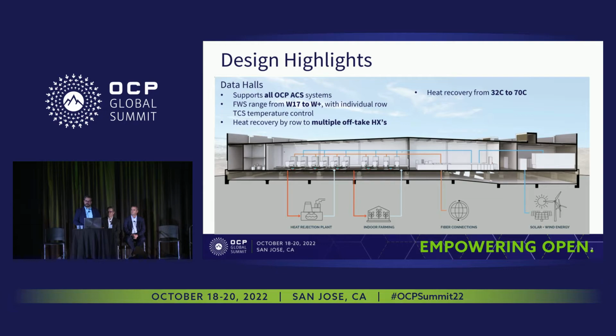At the ITE environment, a data hall level, all of those choices allow us to use and support all types of advanced cooling technologies and systems in accordance with OCP. So we are agnostic on technology at the rack level or ITE cooling level—we can use immersion, rear door heat exchangers, or cold plates. It really doesn't affect the performance of the facility because it's agnostic with the choices we've made so far in the design.